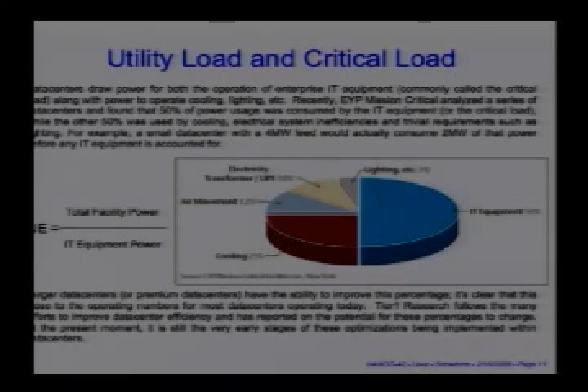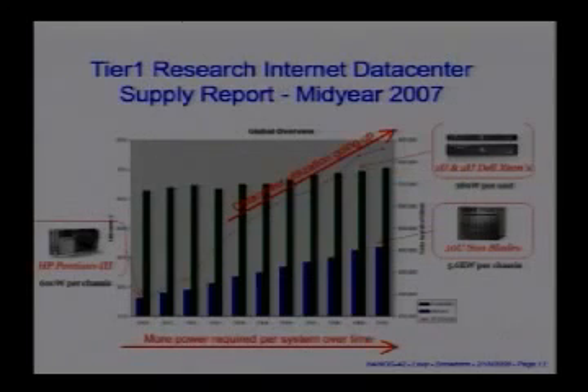When you get out to buildings running in the multi-megawatt range, that 3% can actually relate to real money at the end of the year. This is a report from Tier 1 from the middle of last year, which talks about internet infrastructure data centers — not enterprise — and the amount of utilization, the amount of space available. That number has grown from the 25 to 30% range in 2002 all the way up to the 50 to 55% range today. That's the utilization. But what's happened in parallel is that what goes into those data centers has also increased — the multiplier here is the power usage.